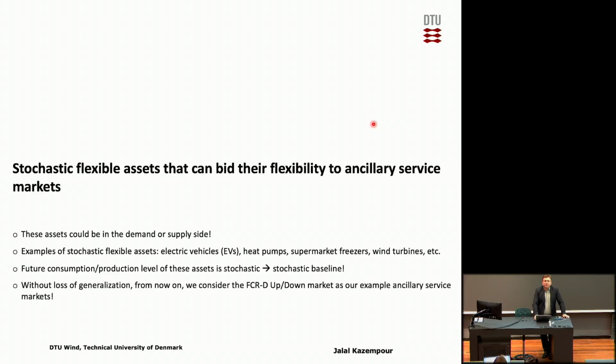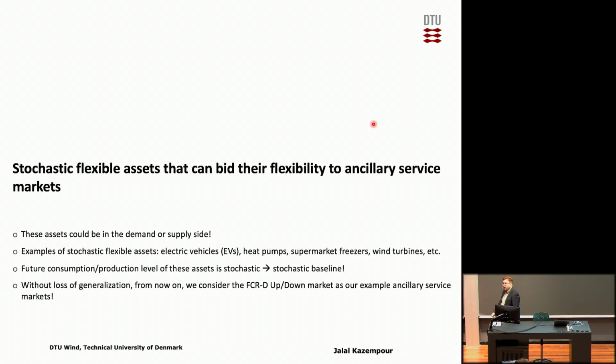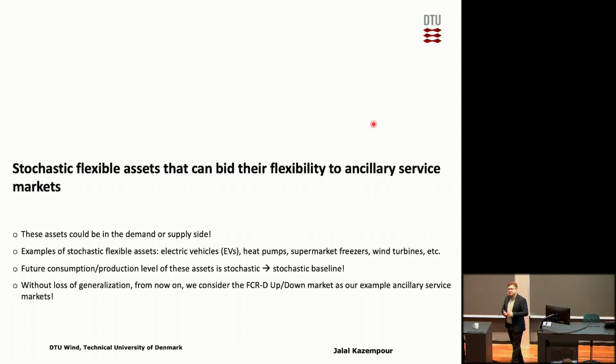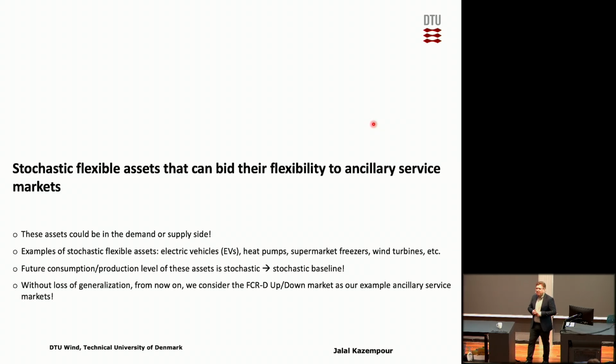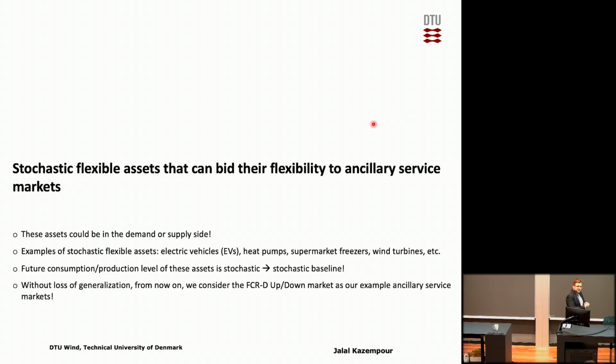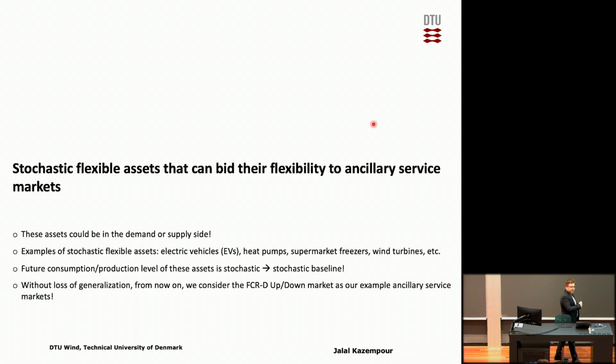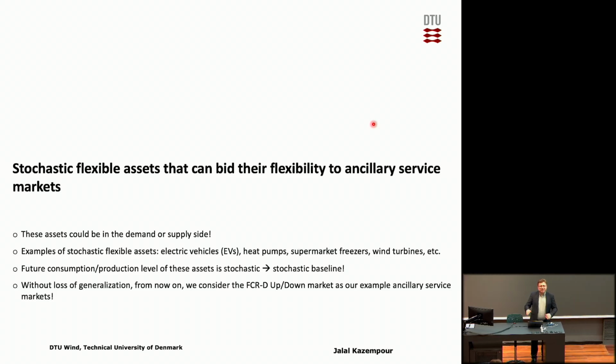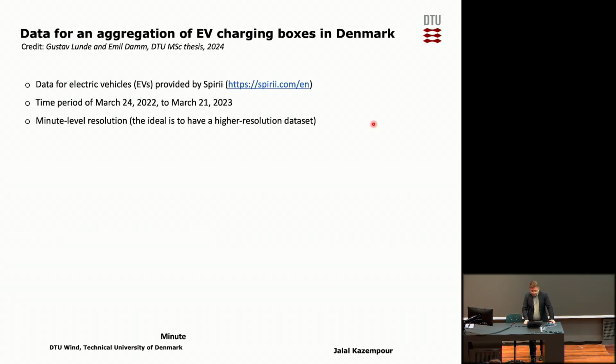So here I can only talk about participating in FCR-D markets, up and down, but the same concept you can consider for any other ancillary service markets like aFRR or mFRR. Maybe for mFRR it will be a bit harder, more complex than what I'm going to present, because mFRR is an energy intensive service, while FCR-D is not. When it's being activated, the energy being charged or discharged is kind of negligible, because the duration of activation is very short. Good.